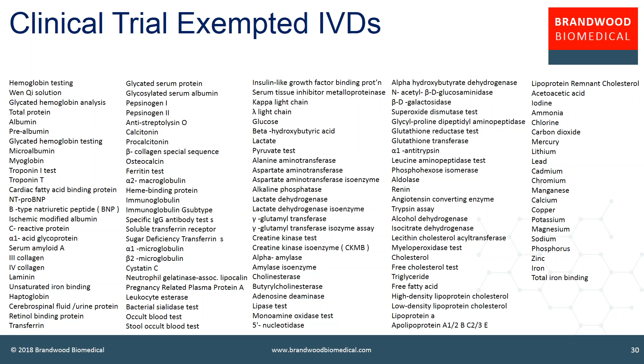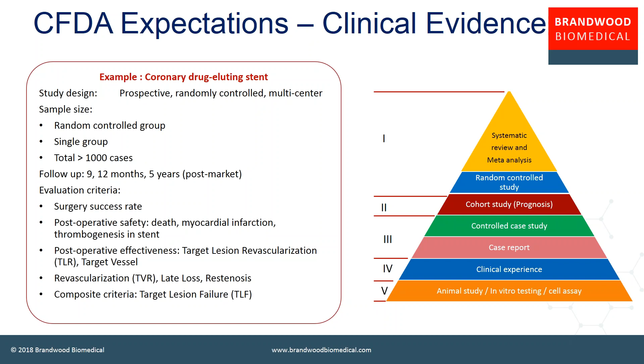Now, exempted devices still require comparison to a predicate, and it has to be an in-China registered predicate. And you'll recognize this sort of table as really borrowed straight from the US FDA practice. There is a guidance. Here's the announcement on the CFDA website, and in your handouts you'll see an English language translation of the China guidance. And we'll just look a little bit at what that guidance says. Same things you see as you see in the European and Australian guidances. Levels of evidence appears, specific requirements for certain devices.